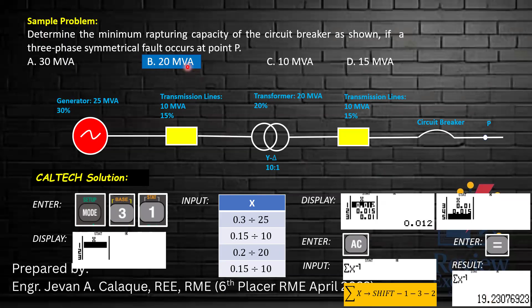19.23. So yung ating fault current or three-phase symmetrical fault current is 19.23, and that is approximately equal to 19.23 MVA, and that is approximately equal to 20 MVA. Okay? So let's try to solve our problem from the very start.